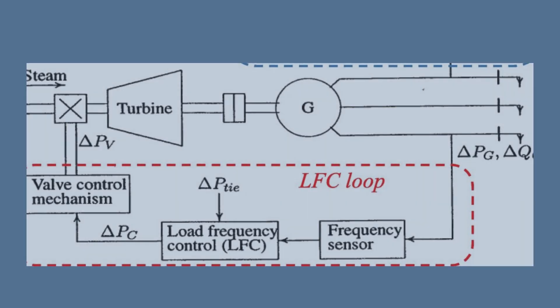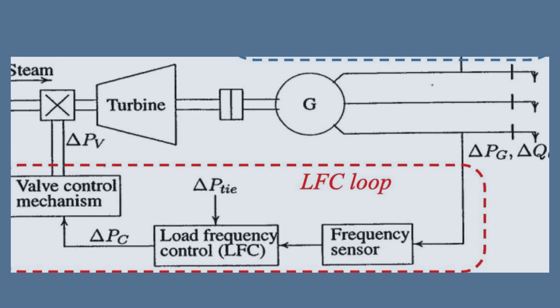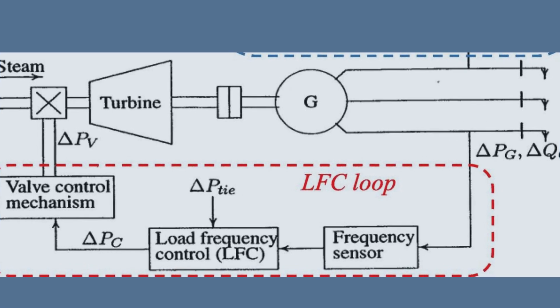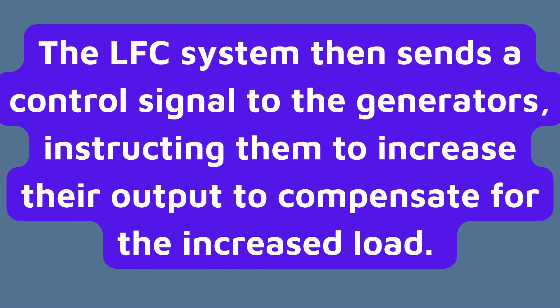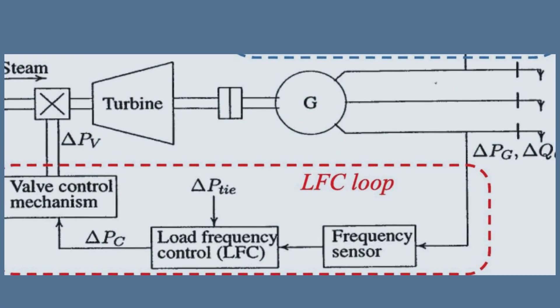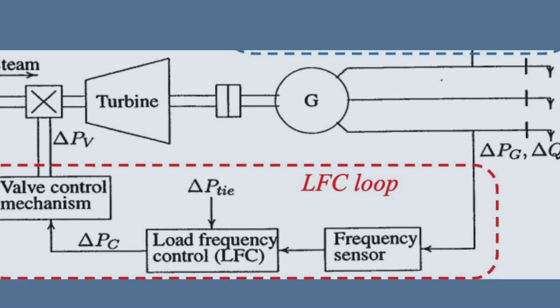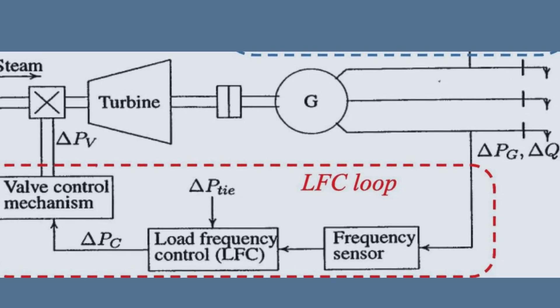Now, let's break down how LFC works. When there's a load change in the system — say, a large industrial plant turns on — a few things happen. First, this increase in load causes the system frequency to drop. Sensors detect this frequency change and send the information to the LFC system. The LFC system then sends a control signal to the generators, instructing them to increase their output to compensate for the increased load. This feedback loop continues, constantly adjusting the generator output to keep the frequency stable.